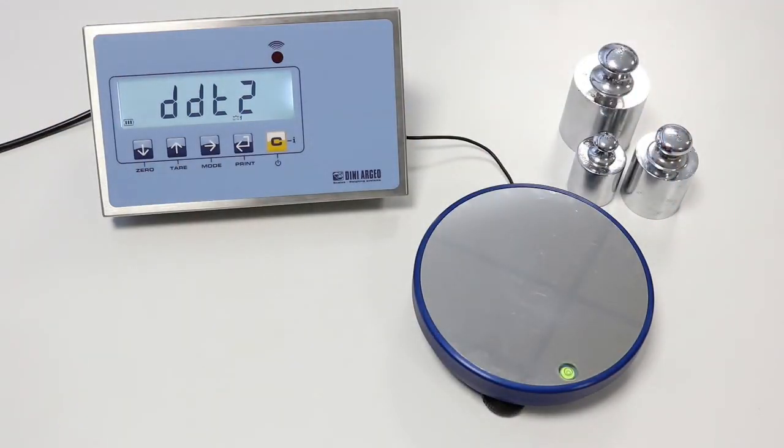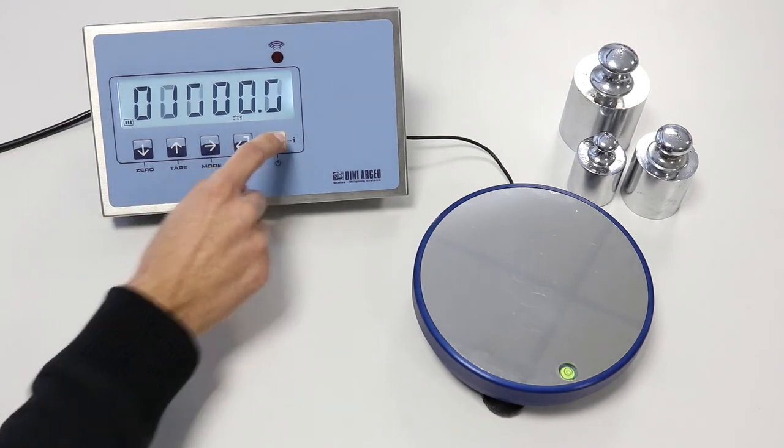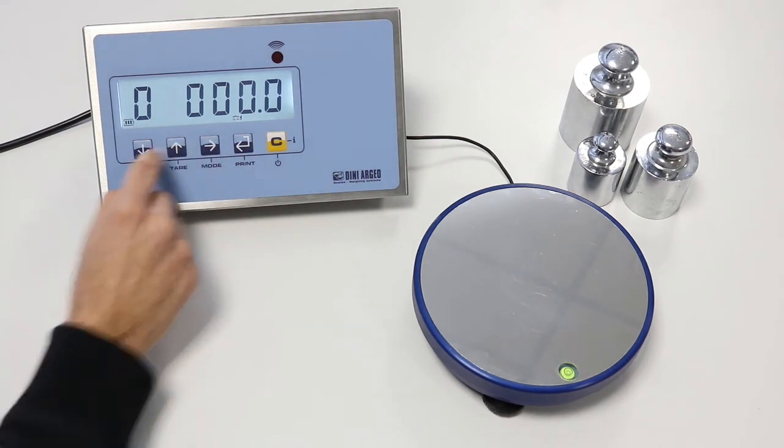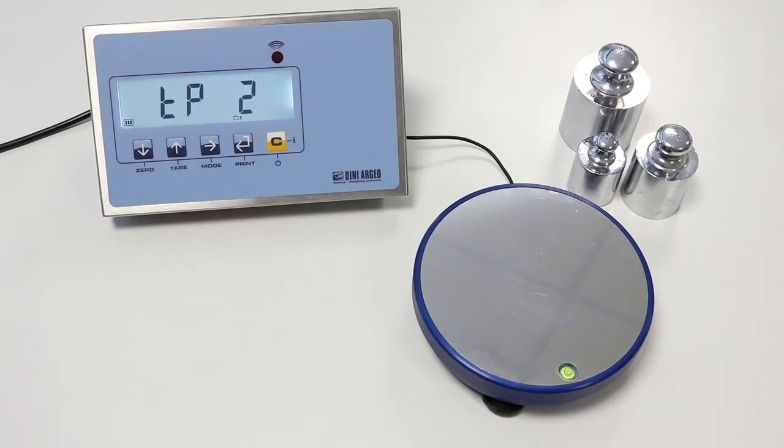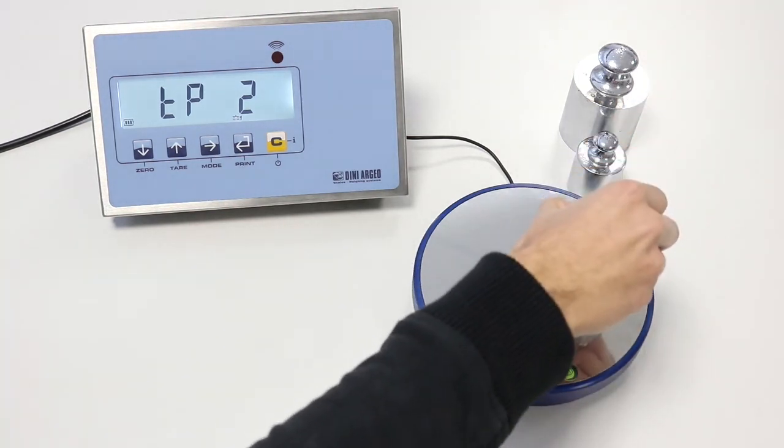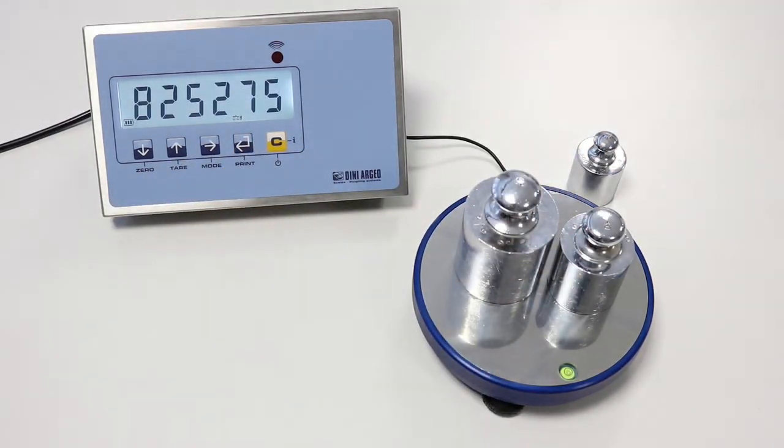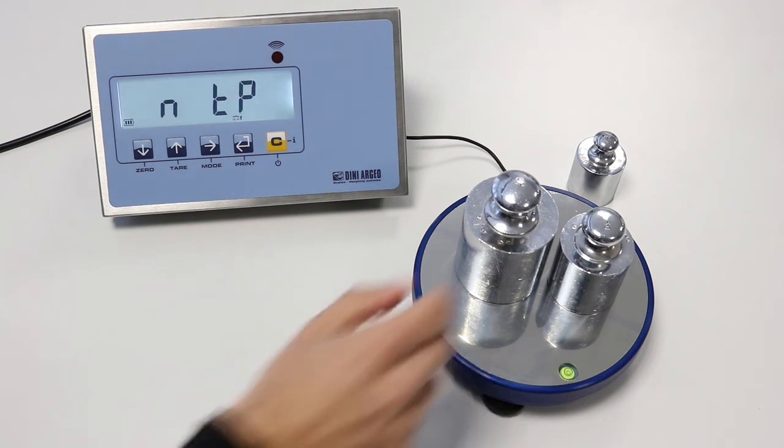DDT2 is the second calibration point. We repeat the same operation as before. We set 3000 grams and confirm with PRINT. TP2 appears. We load the sample weight on the scale. We confirm and wait for the acquisition. OK, calibration is done and we can unload the scale.